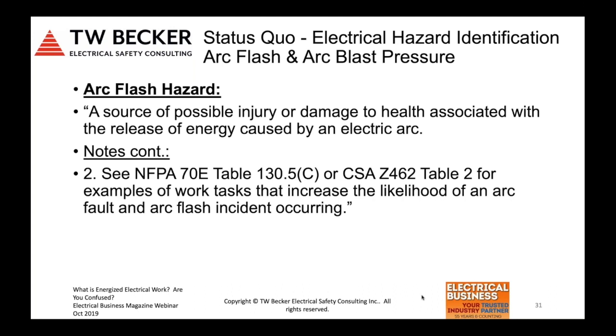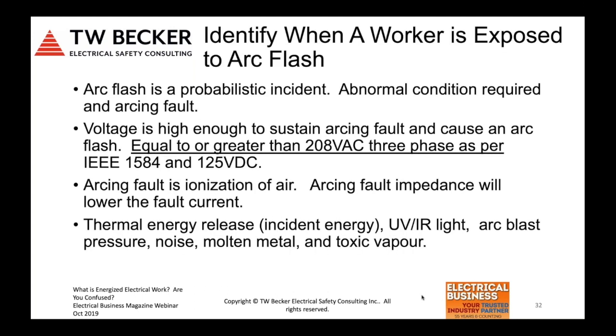So another slide on arc flash: it's a probabilistic incident. An abnormal condition is required, an arcing fault. And again, the abnormal condition could be by worker interaction or without worker interaction. And when can an arcing fault occur? Right now, the threshold is 208 volt 3-phase, and dependent on the fault current, we could have a sustainable arcing fault and arc flash. And for DC, 125 volts DC, again, depending on the actual electrical equipment that voltage exists on. Arcing fault is ionization of air.